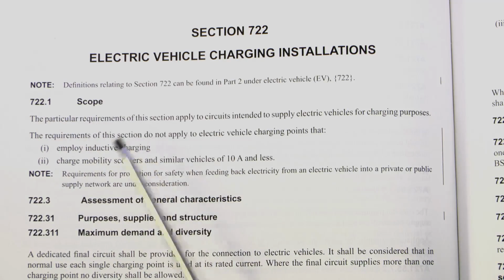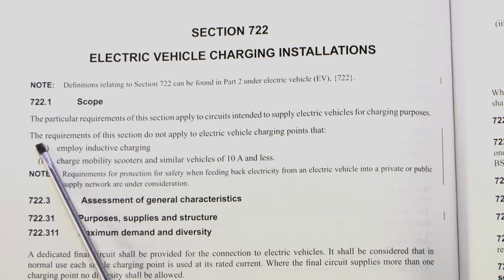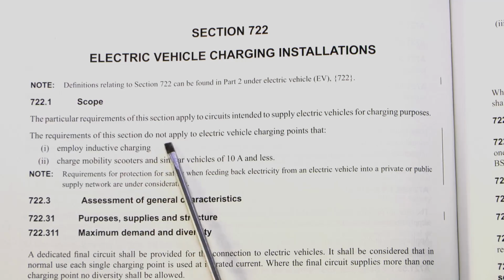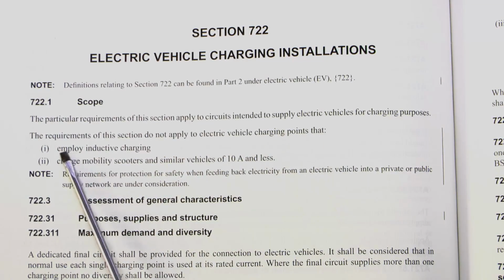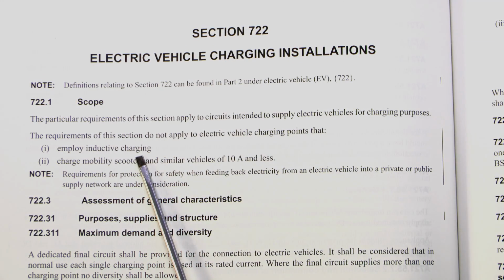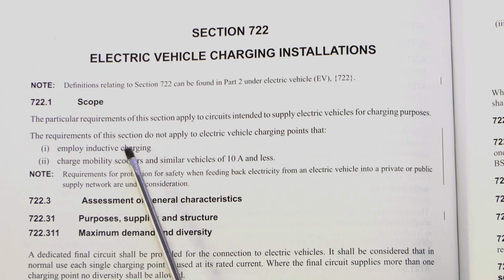722.1, the scope, has a minor change in that we've now got the requirements of this section do not apply to electric vehicle charging points that employ inductive charging. So that has now been added in there, and that's essentially where it's not a direct electrical connection, it's just going to be, as it says, an inductive or a magnetic connection between the actual vehicle and the charging equipment. So this only applies where we've got a direct plug-in or electrical connection to that.